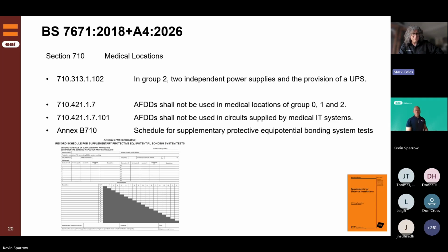The next two regulations concern AFDDs, which have been a big discussion point. The reason they don't want them in hospitals is, of course, they don't want something tripping out unnecessarily. The rationale in medical locations is that systems are being monitored all the time, with a rolling program of maintenance keeping on top of everything, so they don't expect arcing to occur because the installation isn't expected to deteriorate. That's where the AFDD exemption comes from.